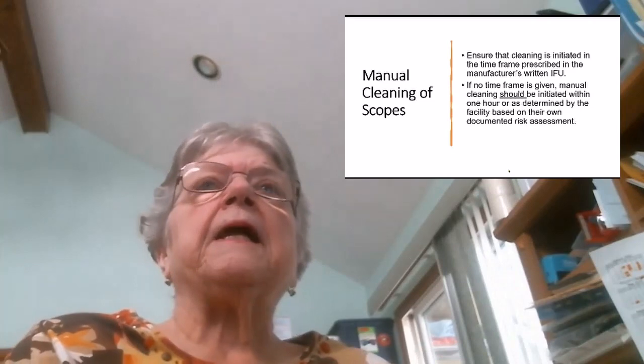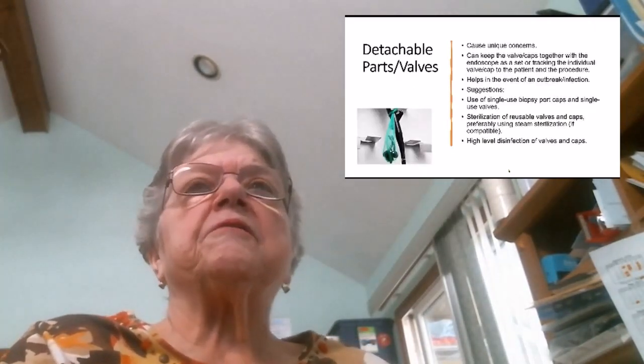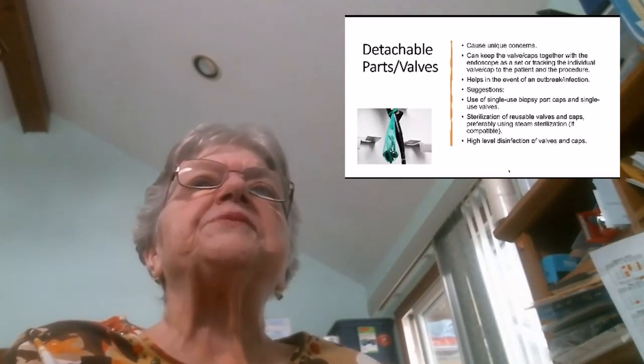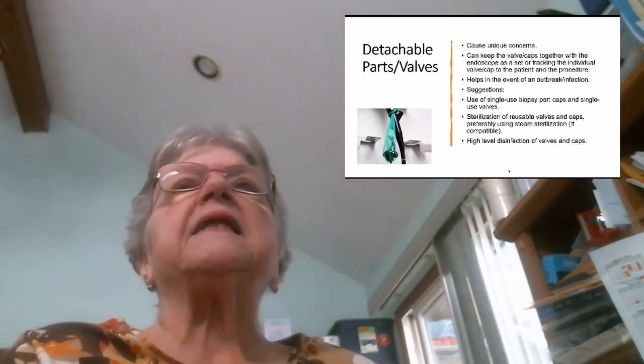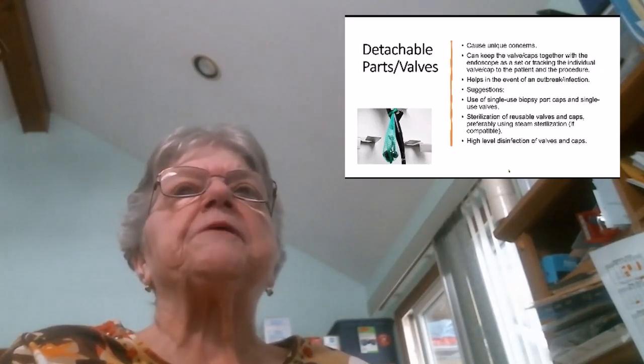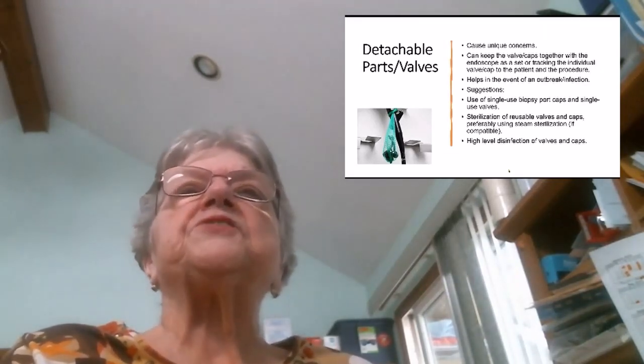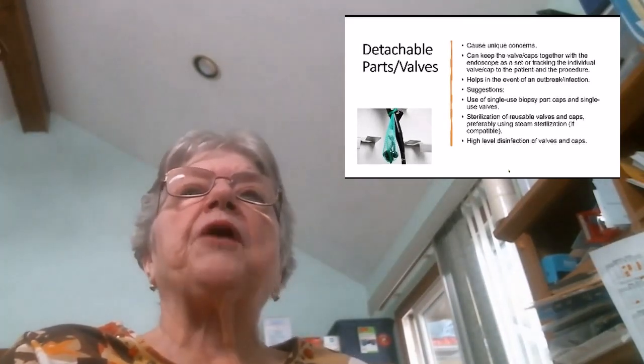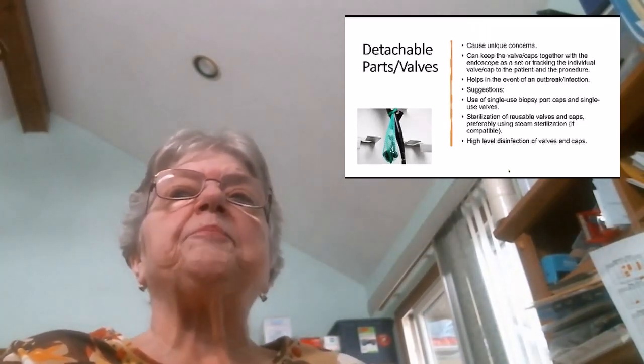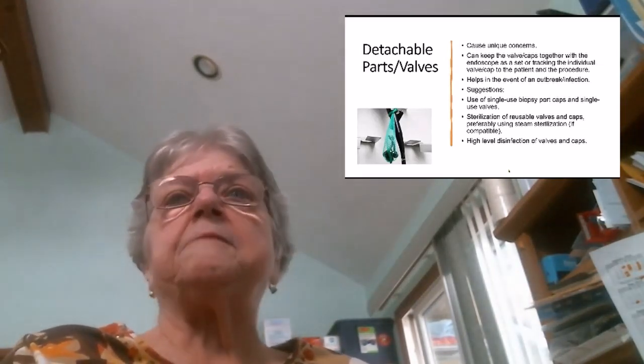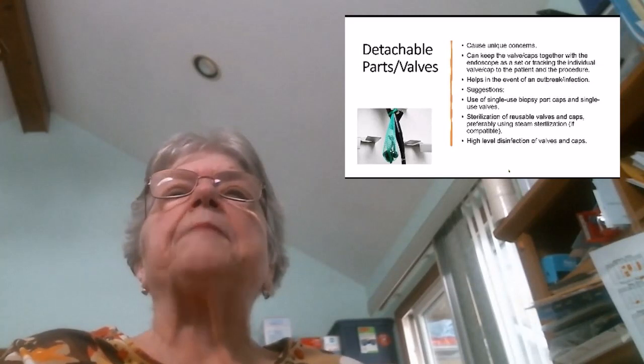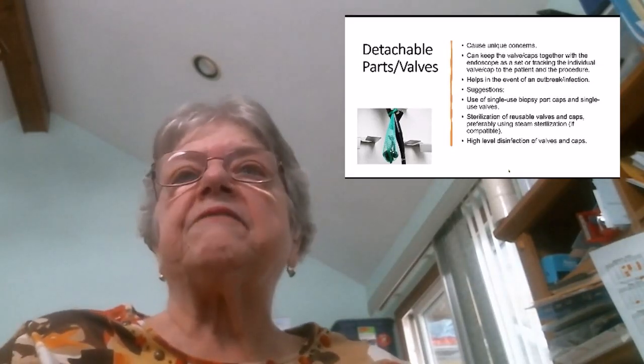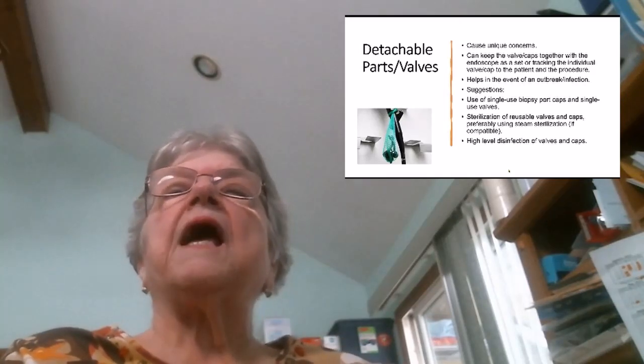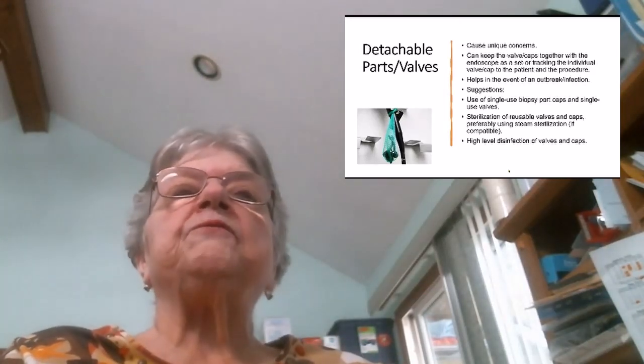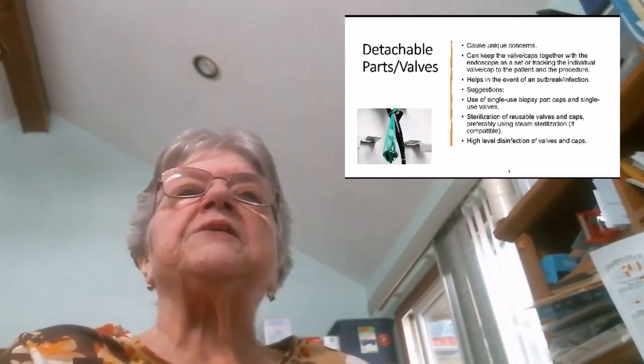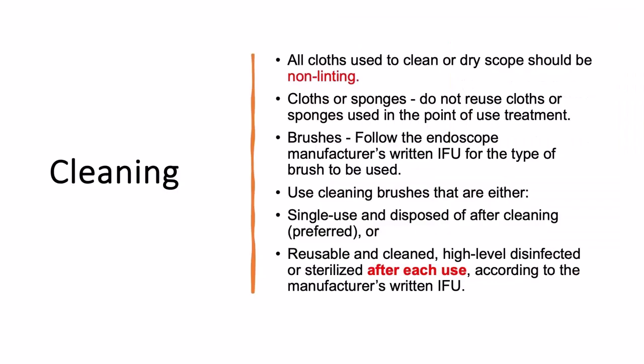That's just my opinion. Detachable parts and valves. These are a concern. You should keep the valves and caps together with the endoscope as a set, or track the individual valve or cap to the patient and the procedure. This helps in the event of an outbreak of infection, because it could be the valve or cap was part of the problem. Now, you can use single-use biopsy port caps and single-use valves, which a lot of people have done. You can sterilize reusable valves and caps using steam sterilization if it's in the IFU, or they can be high-level disinfected if it's in the IFU. But if you use the reusable, they need to be kept with the scope, and there are many devices on the market that will help you do that.